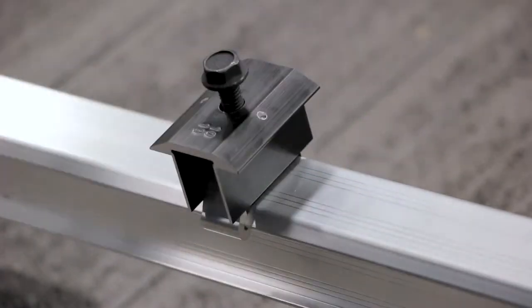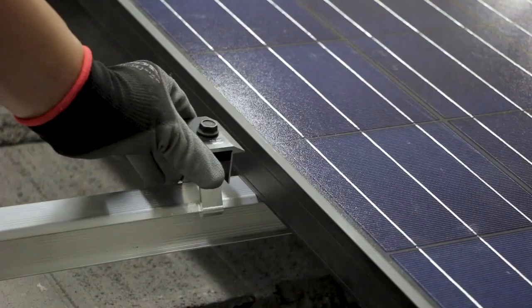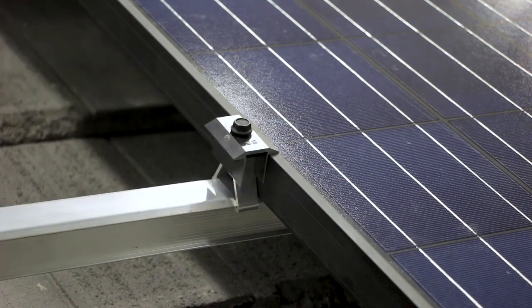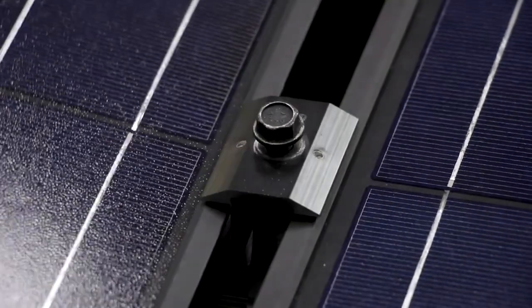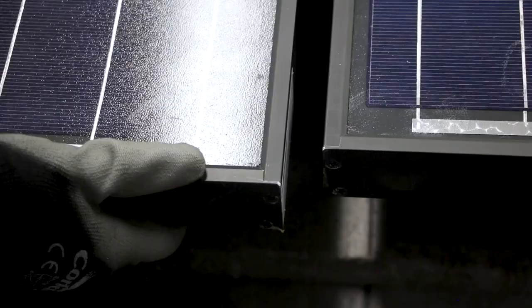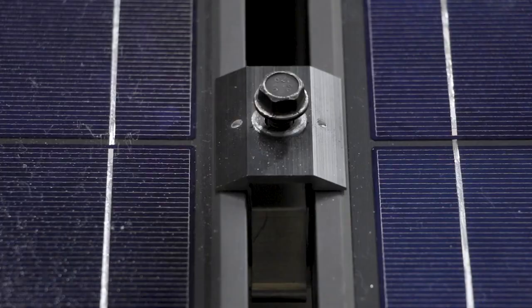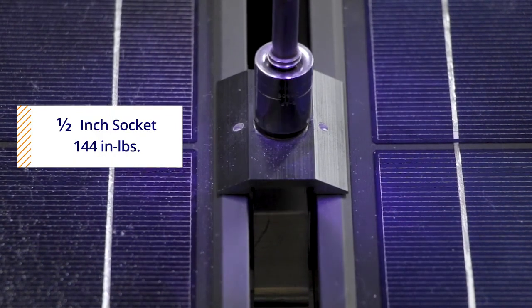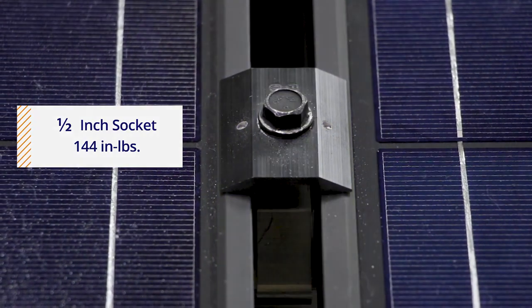Click the mid-clamp onto the top of the ClickFit rail and then slide it flush against the side of the module frame. Then, slide the next module in the row up against the other side of the mid-clamp. Align the bottom edges of the modules, and then check to assure that both modules are pressed flush against both sides of the mid-clamp, and that the head of the mid-clamp is resting flat on top of both of the module frames. Tighten down the mid-clamp to 144 inch-pounds using a 1/2-inch socket.